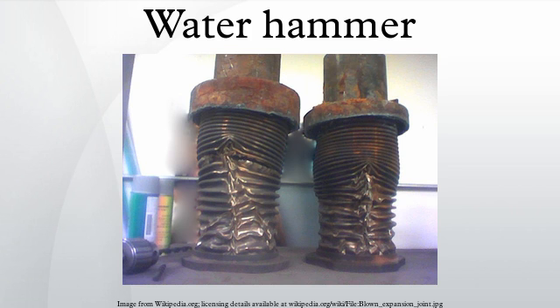The more sophisticated packages may have any of the following features. Multiphase flow capabilities, an algorithm for cavitation growth and collapse, unsteady friction, the pressure waves dampen as turbulence is generated and due to variations in the flow velocity distribution, varying bulk modulus for higher pressures, fluid structure interaction, the pipeline reacts on the varying pressures and causes pressure waves itself.